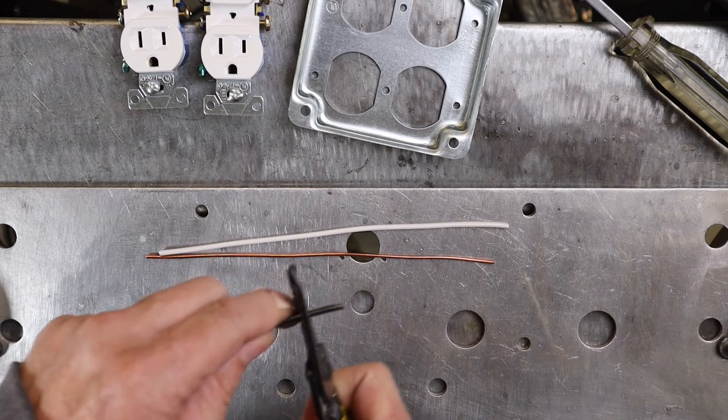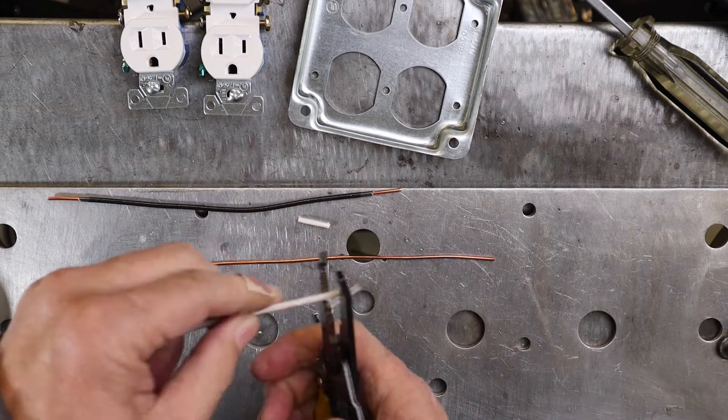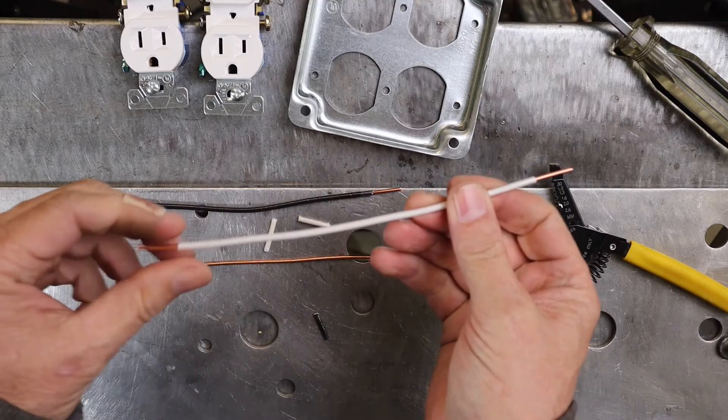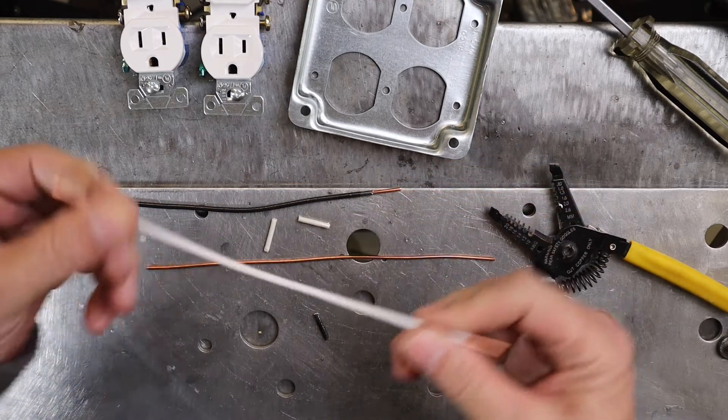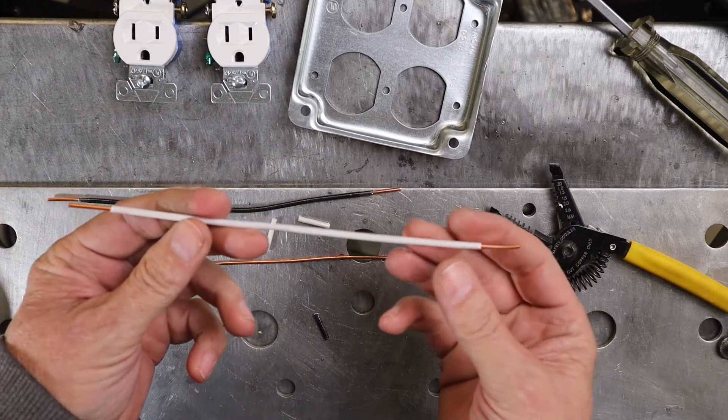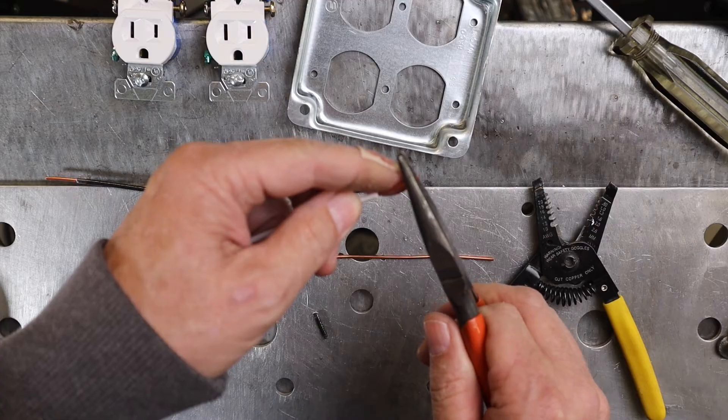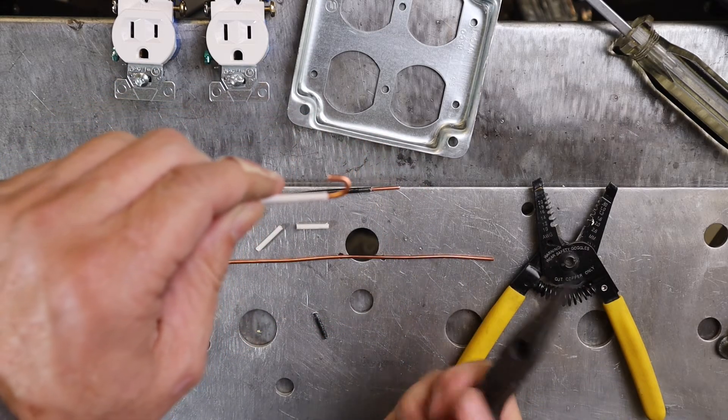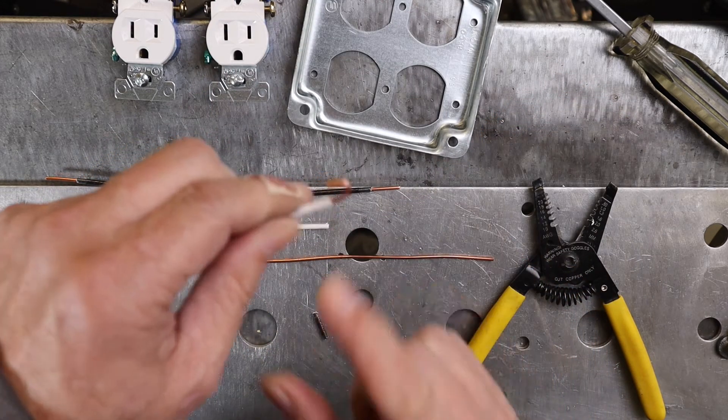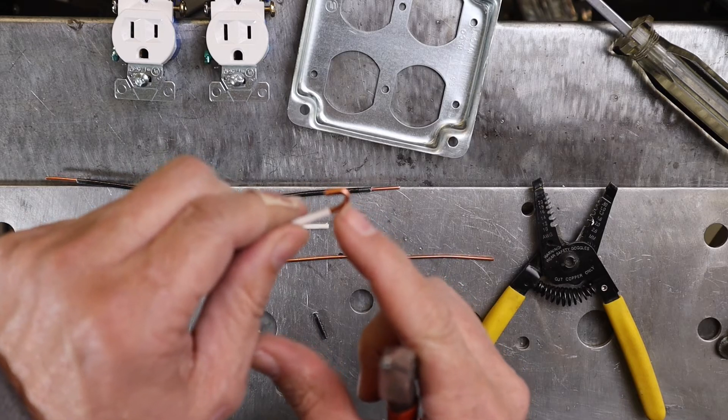You want to strip enough of the insulation so that when you make the hook, there's no insulation going to be incorporated into that hook. As you tighten it under that screw, the screw is tightening down just on the copper, not on the insulation. Then I'll take one end of each one of those and bend a hook into it. Here's where you got to be real careful: if you don't strip enough, you don't want that insulation coming up here into the hook where that screw is.